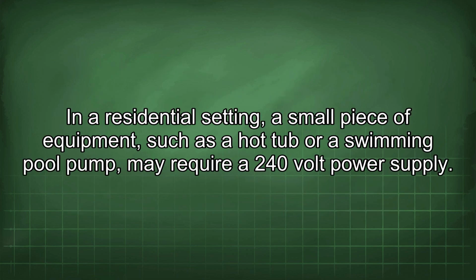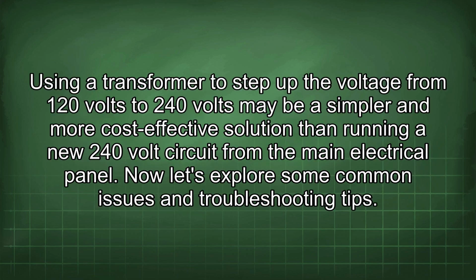In a residential setting, a small piece of equipment, such as a hot tub or a swimming pool pump, may require a 240-volt power supply. Using a transformer to step up the voltage from 120 volts to 240 volts may be a simpler and more cost-effective solution than running a new 240-volt circuit from the main electrical panel.